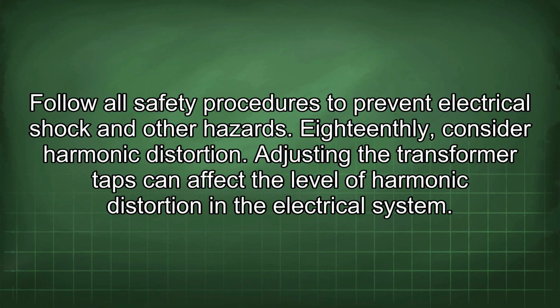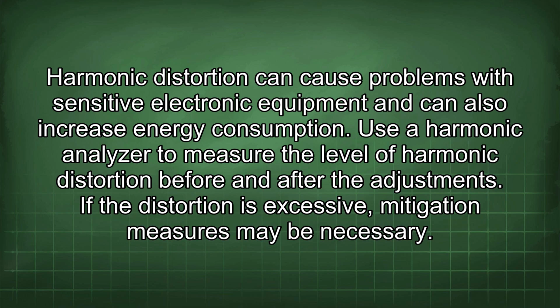18thly, consider harmonic distortion. Adjusting the transformer taps can affect the level of harmonic distortion in the electrical system. Harmonic distortion can cause problems with sensitive electronic equipment and can also increase energy consumption. Use a harmonic analyzer to measure the level of harmonic distortion before and after the adjustments. If the distortion is excessive, mitigation measures may be necessary.